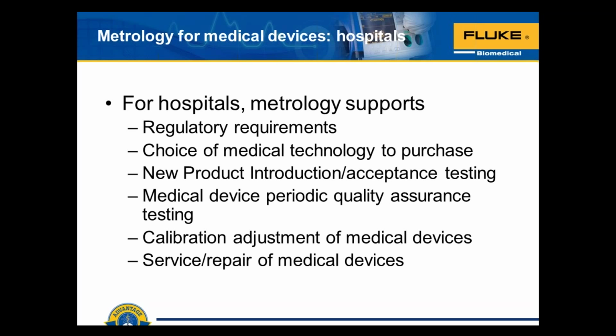For hospitals, that's you and me. The metrology supports our regulatory requirements under the FDA, the choice of medical technology that you're going to purchase, new product introduction acceptance testing. So you should always do acceptance testing of the medical devices that you're going to be purchasing. Medical device periodic quality assurance testing, that's what you do in preventive maintenance all the time. Calibration adjustment of the medical devices and the service and repair of those medical devices and the test instruments that you use. So it affects all of those areas.